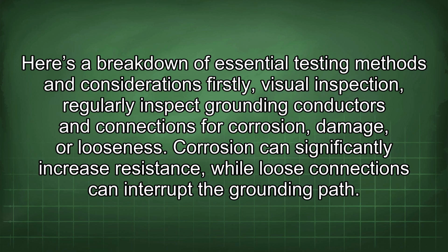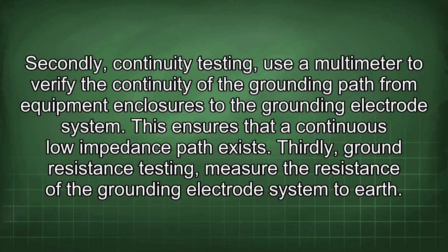Firstly, visual inspection. Regularly inspect grounding conductors and connections for corrosion, damage, or looseness. Corrosion can significantly increase resistance, while loose connections can interrupt the grounding path. Secondly, continuity testing. Use a multimeter to verify the continuity of the grounding path from equipment enclosures to the grounding electrode system. This ensures that a continuous low impedance path exists.